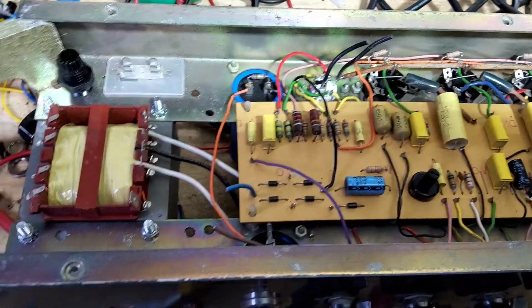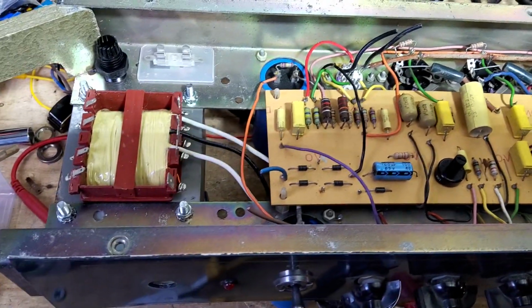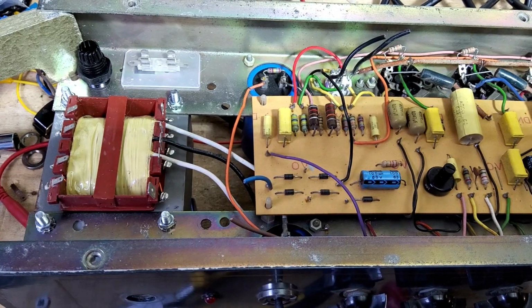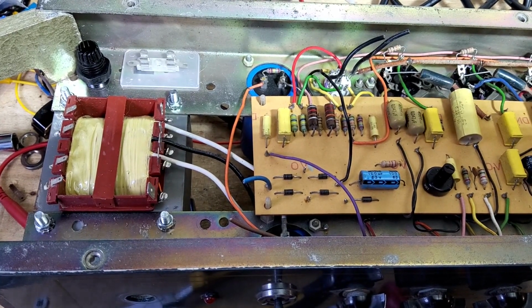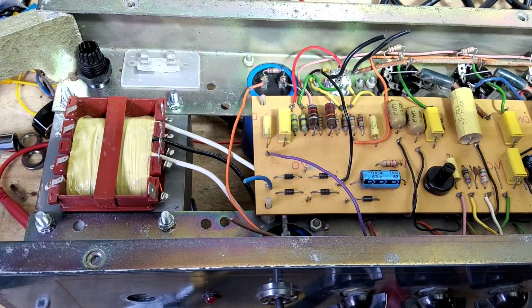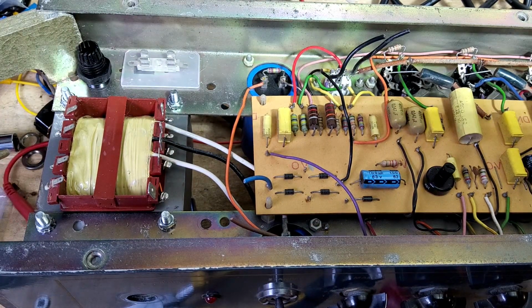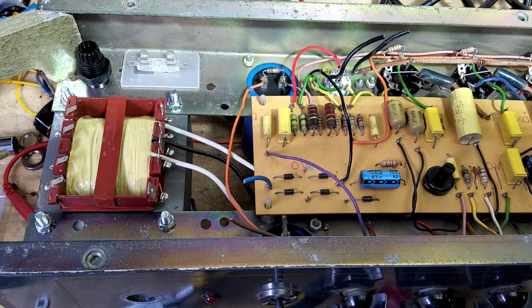And then we've got the HT. Now the HT is 372 volts AC. When we've rectified that and smoothed it to DC, we'll have 520 volts off this transformer, because it's times by 1.4 - I think it's 1.414, but 1.4 is close enough. So we'll have about 520 volts.